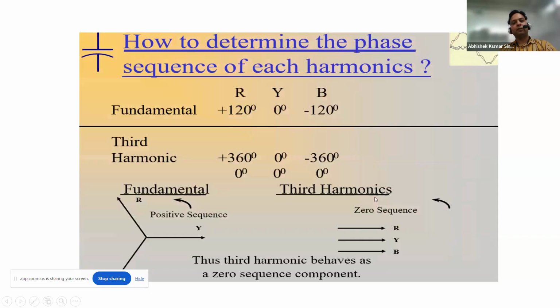Now we will understand the third harmonic, third sequence, not harmonic, sorry. For the third sequence the difference will be 360 degree. 360 degree means from where you start, you come back to the same point. It means all the harmonic currents generated in zero sequence will be in the same phase. This is generally produced by single phase loads, and all the current will travel into the neutral, and the neutral current will go into the source. So our source neutral will get overheated along with the core of the transformer. So negative and zero sequence harmonics are more dangerous as compared to positive. If the neutral is getting overloaded or overheated, it means there is a presence of zero sequence. If our motor is not moving properly, it means there is a negative sequence, because negative sequence will always oppose the rotation.